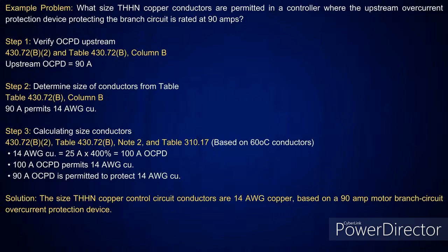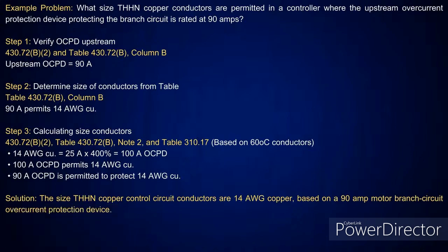If you look at the bottom of the table, it's going to tell you that it's based on table 310.17, and I'm going to use a 60-degree C column. So when you go over and look at table 310.17, you pick up the number 14 copper conductor. It's going to tell you it's good for 25 amps. But right below that table, in note 2, it's going to tell you take it at 400%. If you take 400%, that gives you 100 amps, which permits the number 14 conductor. Therefore, that 90 amp is permitted to protect those number 14 conductors.